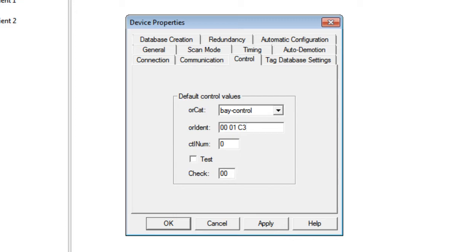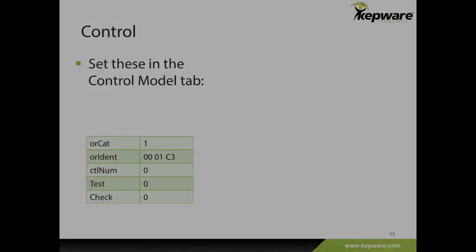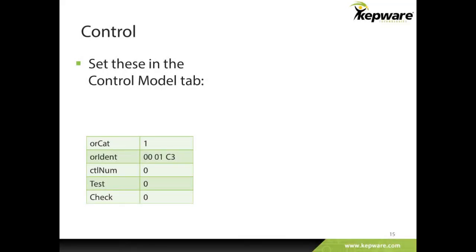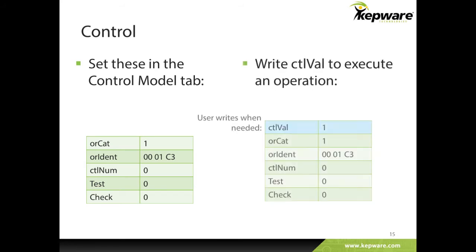To set the control model for data attributes in the CO functional constraint, simply enter the required information such as orcat or orident in the device properties control tab. When users wish to change a control value, for example turn a switch on or off, they will be able to write to a controllable object's control value tag without having to specify the static information of orident or orcat every time.